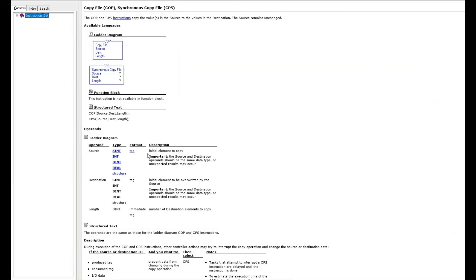The key reason is that COP always expects the same data types. In the help documentation, it says the source and the destination must be the same data type, otherwise unexpected results will occur. In this case, the destination and source data type is the same, but the structure is a little bit different, and that is causing the problem. I will show this case.